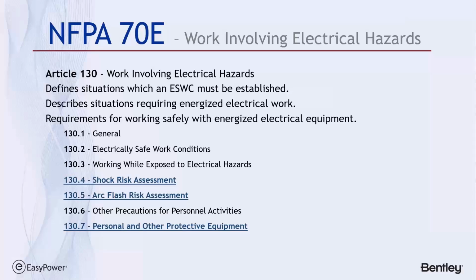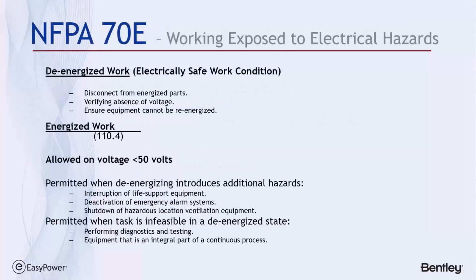Starting in Article 130, there's a description of electrical work that can and can't be done, and the requirements of doing the hazard assessment in the process. The two primary risks that we're concerned with are electric shock and arc flash, and they are covered in 130.4 and 130.5. So going back to NFPA 70E, it says de-energized work is the only safe work condition, and that's their baseline. But then starting in 110.4, it talks about what's allowed for hot work if necessary. For starters, anything below 50 volts we're allowed to work on without being concerned about arc flash hazard or electrical safety.